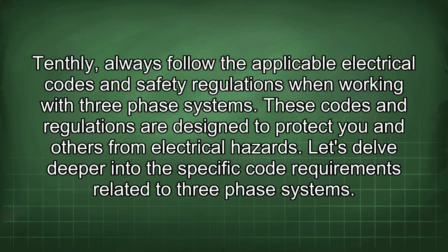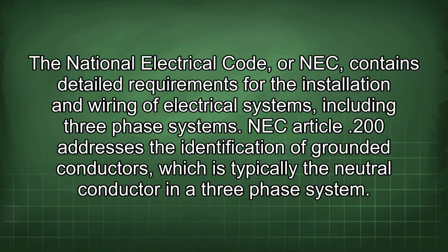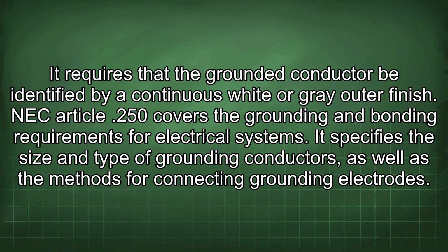These codes and regulations are designed to protect you and others from electrical hazards. Let's delve deeper into the specific code requirements related to three-phase systems. The National Electrical Code, or NEC, contains detailed requirements for the installation and wiring of electrical systems, including three-phase systems. NEC Article 200 addresses the identification of grounded conductors, which is typically the neutral conductor in a three-phase system. It requires that the grounded conductor be identified by a continuous white or grey outer finish.